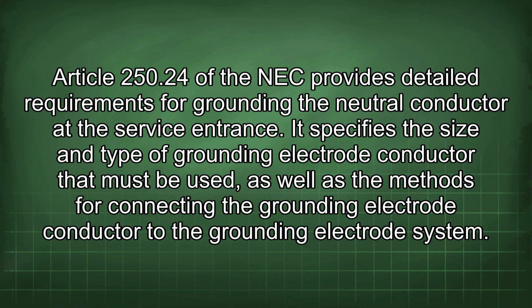Article 250.24 of the NEC provides detailed requirements for grounding the neutral conductor at the service entrance. It specifies the size and type of grounding electrode conductor that must be used, as well as the methods for connecting the grounding electrode conductor to the grounding electrode system.